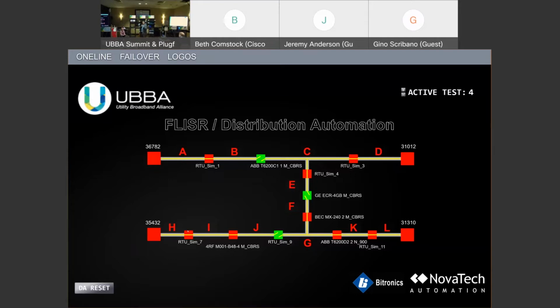So the reclosers operate faster. They cause a transient for more customers. But when the transient clears, they can re-energize. And most of the time, that's better for the vast majority of customers. So we use comms to switch back and forth between those modes sometimes. It's kind of a big button, even in the control center. They can say, oh, we're going to switch modes, or they can highlight an area, say, hey, for these feeders, we're going to switch modes. We do it different ways for different scenarios.